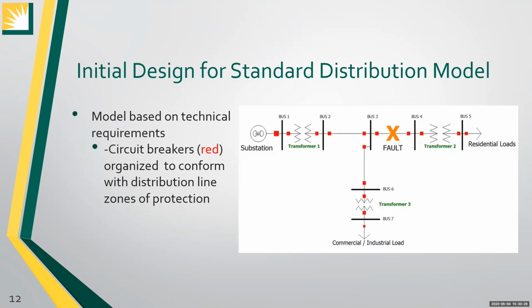To get to our final model, we went through a process. We began with an initial design for our standard distribution model based on the technical requirements established by Southern California Edison, which required the open conductor condition to occur in a residential portion of the electric power system. Our model was designed to include zones of protection, shown in the red boxes, meant to isolate the affected part of the system to ensure delivery of power to other parts of the system.